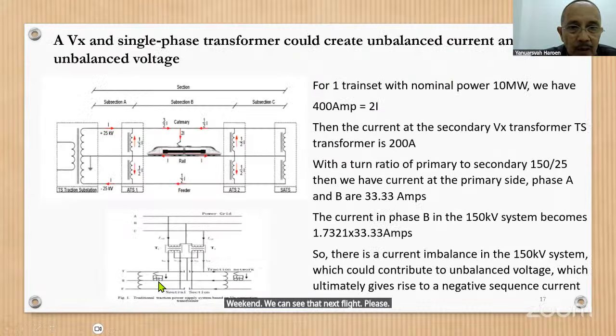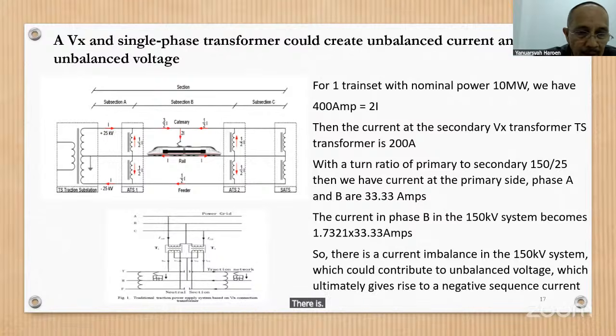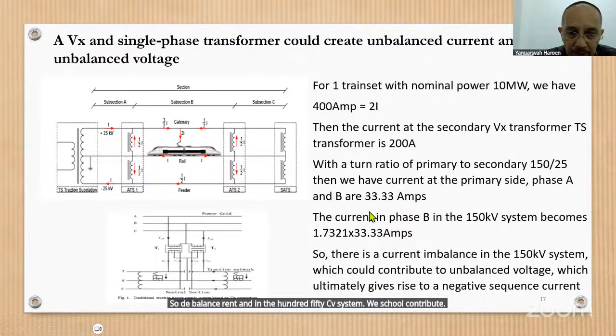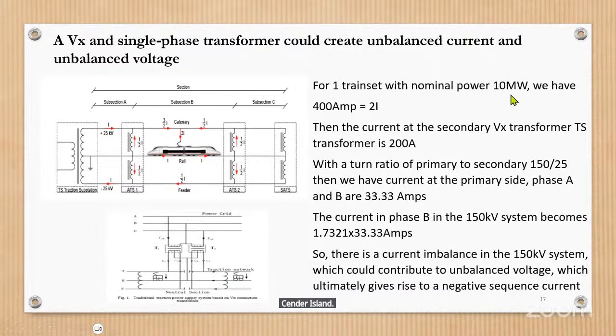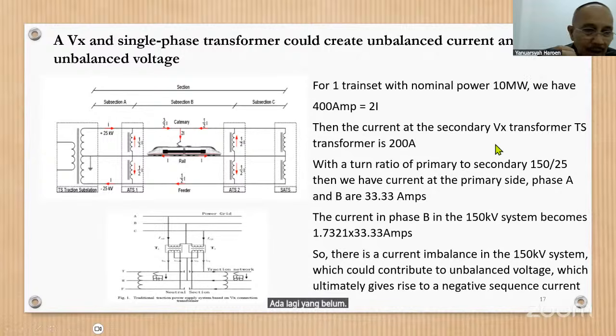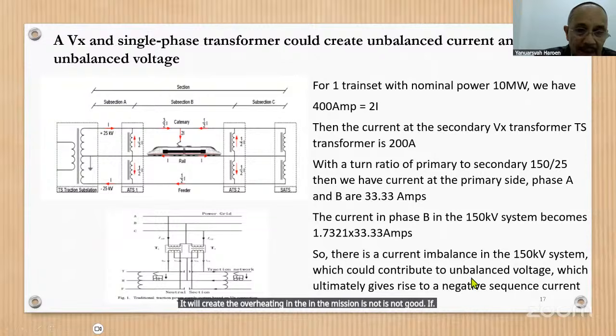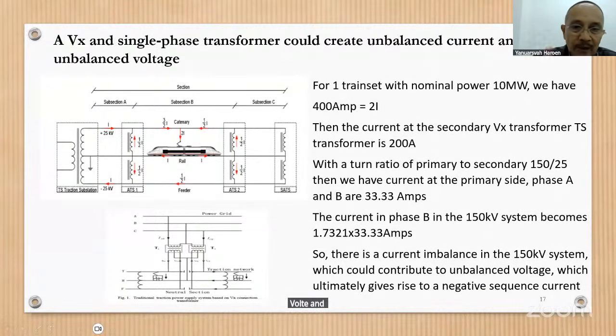There is a current in the first phase B that is not the same as phase A. So this unbalanced current in the 150 kV system could contribute to unbalanced voltage, which ultimately gives rise to negative sequence current. The hydropower plant on the grid will perceive this as double frequency, or 100 hertz, which creates overheating in the machine. It's not good if the voltage unbalance factor is bigger than 1%.